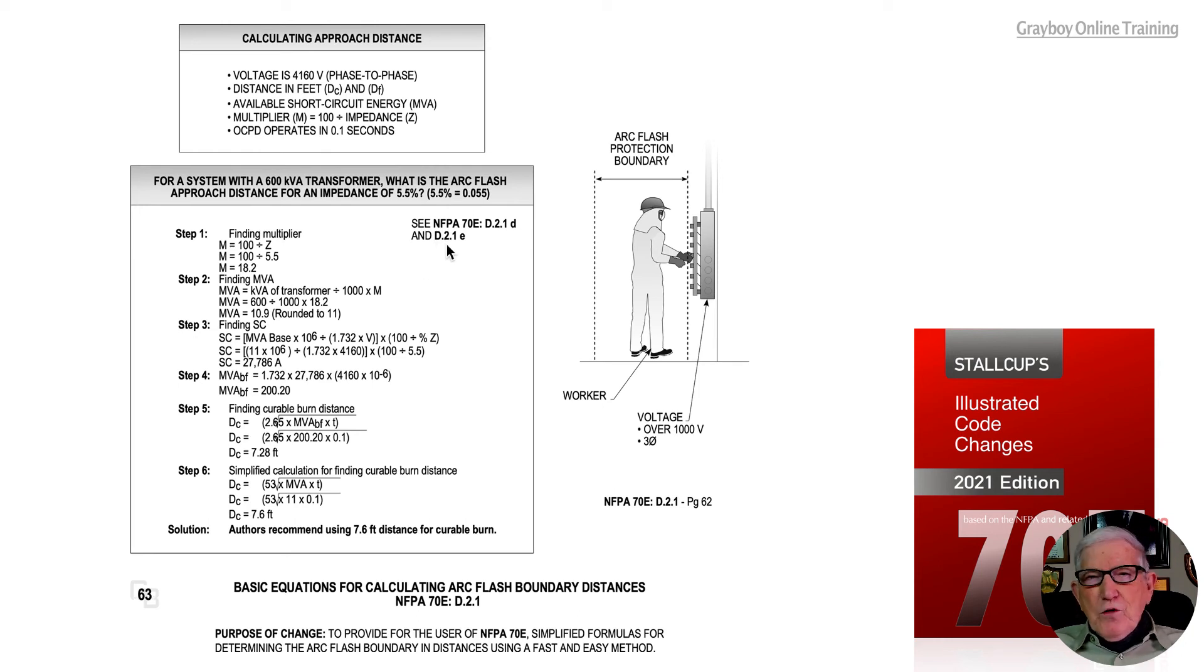Step one, we're going to find our multiplier. We'll take 100 divided by the impedance of the transformer, 5.5. 100 divided by 5.5 gives us a multiplier of 18.2.